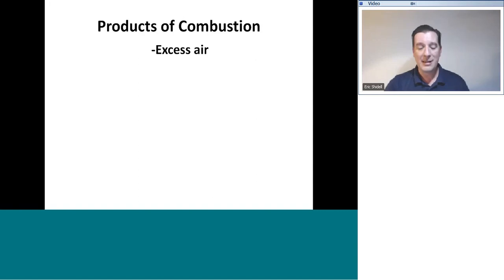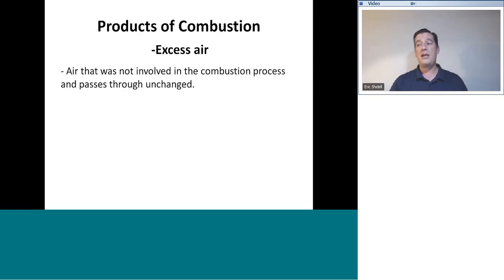Now, the other one isn't necessarily a product of combustion, but a result of combustion, and that's excess air. Remember earlier when I said we give the combustion process additional air, more than it really needs, to ensure that every oxygen molecule has a dance partner that it's able to hook up with? Well, the air that was not involved in the combustion process is going to go right on through the combustion process, literally unchanged. And that's going to be all of our extra nitrogen and that extra 7 cubic feet of air that wasn't required to combine with fuel gas, but we just wanted to make sure that the fuel gas had more than enough.